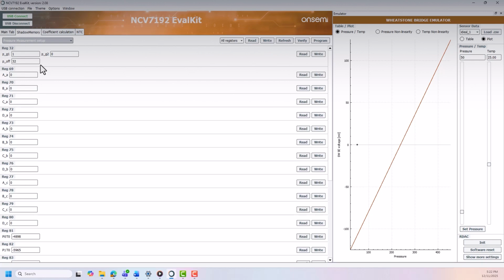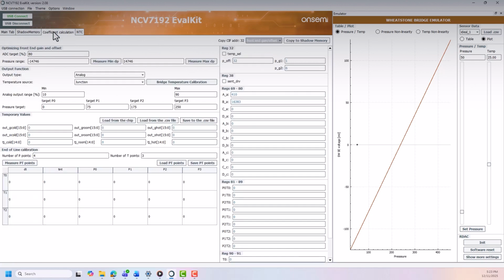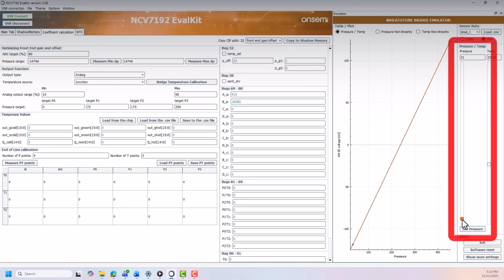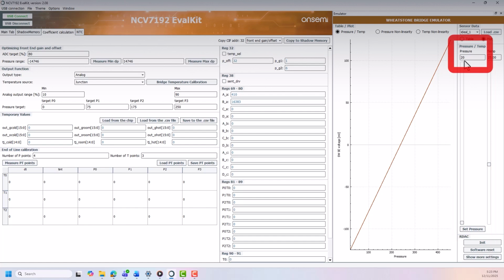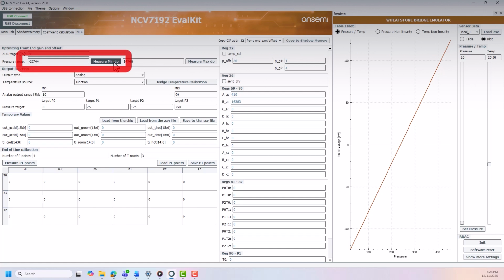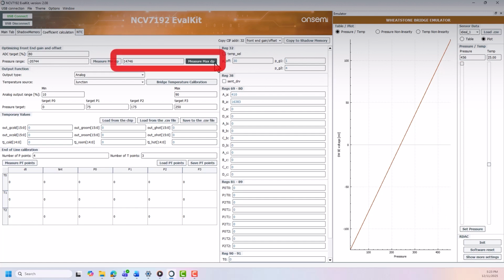Now go to Coefficient Calculation tab. Set on the emulator minimum output voltage by setting lowest pressure. You can move the slider or write pressure number manually. Now click on Measure Min DP button. This will store raw ADC value for minimum pressure. Set maximum pressure on the emulator and click Measure Max DP button. Raw ADC value for maximum pressure is now stored.